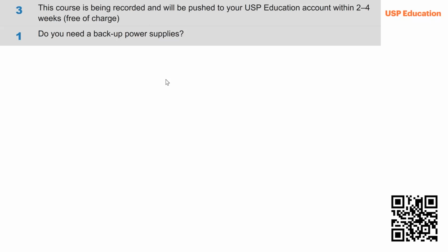Do you need backup power supplies? That's a whole different risk. My easy answer is yeah, you do. There are certain processes and equipment, some PCR systems, where if the system loses power, the run is interrupted and cannot be restarted. If you lose power to temperature control in your equipment or facility, you won't be able to assure the right temperature no matter what. Yes, you need a backup power supply.